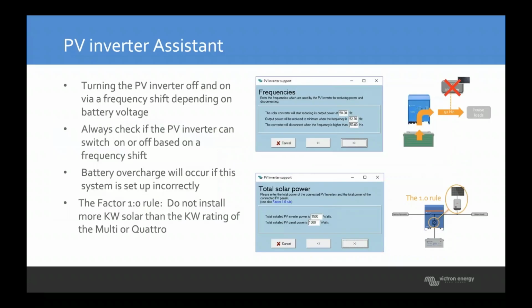The ESS assistant is for grid connected. If you're off-grid, you use the PV inverter assistant, and what this does is it turns on the frequency shift if the batteries need to stop charging. It's very similar to the previous one. Just fill out the wizard, keep the frequency the same as the default in a Fronius system, and set the total PV power in there.